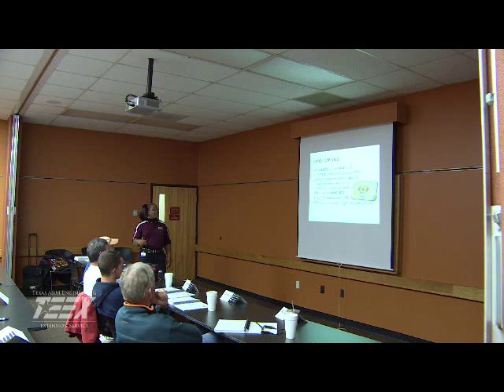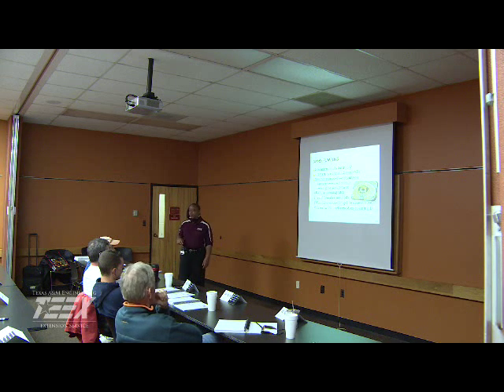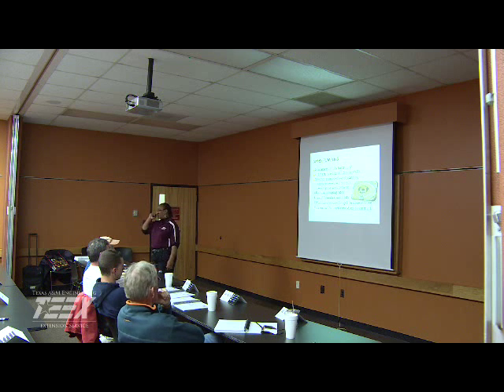EPA recommends less than 5 milligrams per liter by weight, if you want to know where they stood on the sand pumping. Again, you can measure it with the Imhoff cone and calculate the milligrams per liter. But that Imhoff cone is going to give you milliliters per liter.